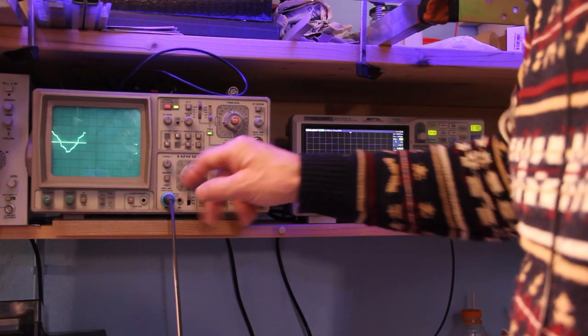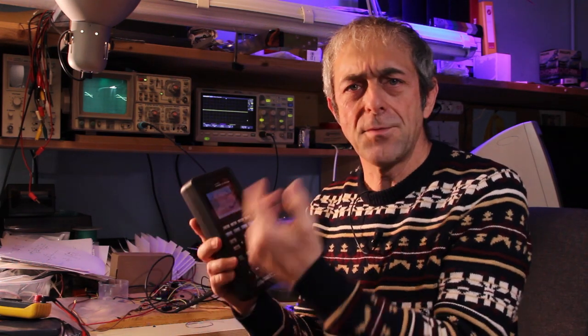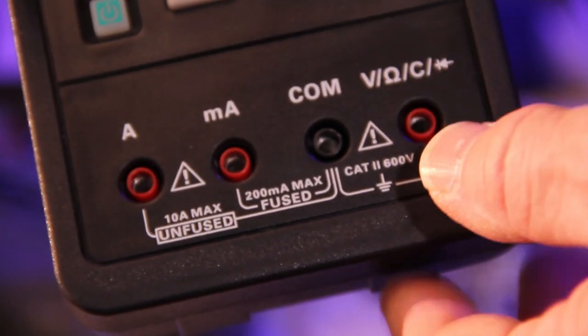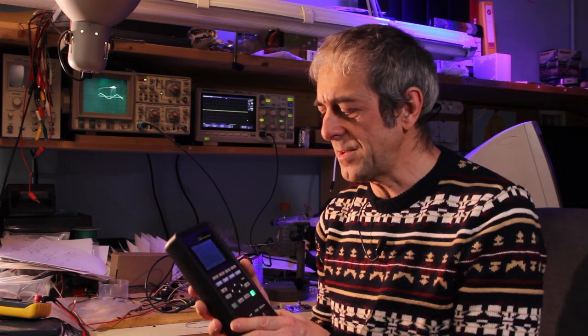All these probes basically convert current or high non-isolated voltages or even other physical quantities into voltage within the range requirements of your oscilloscope. And there are other instruments such as like this one that have a combined function, both multimeter and scope on the same instrument, which is cool. It is portable, easy to carry, and it is fully isolated, so here you don't have to be worried about the possibility of a short between a live wire from mains to ground, provided that the instrument has the right category and enough voltage isolation.